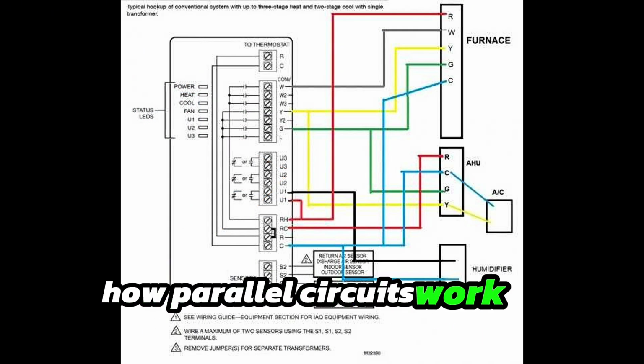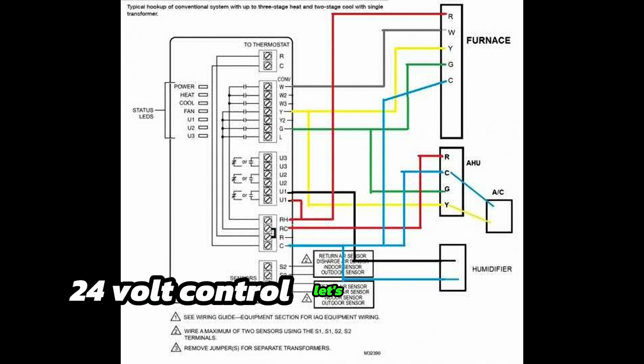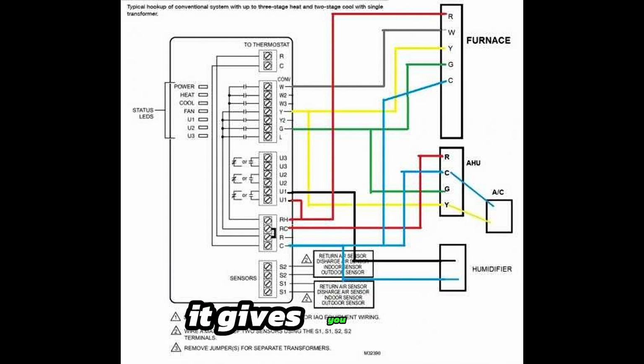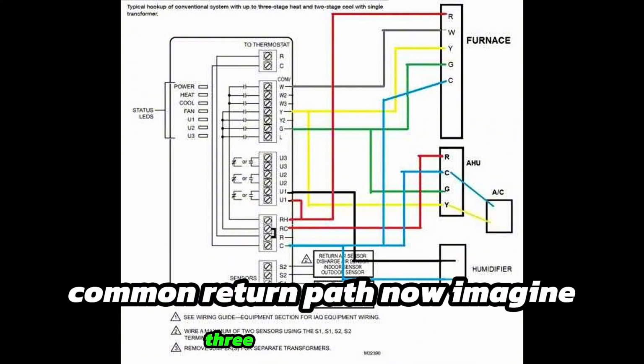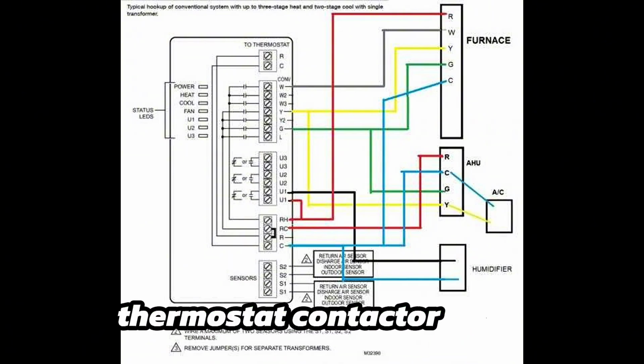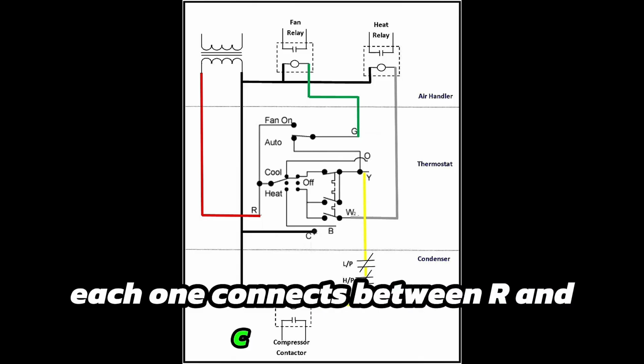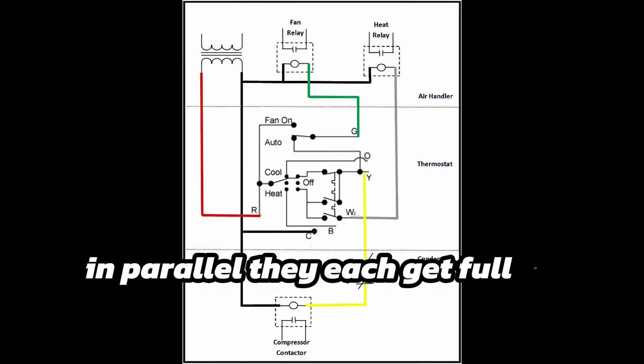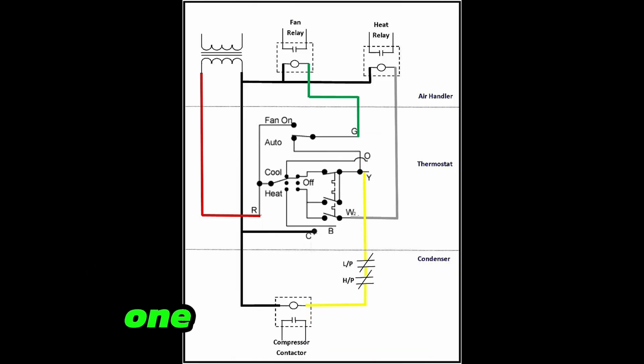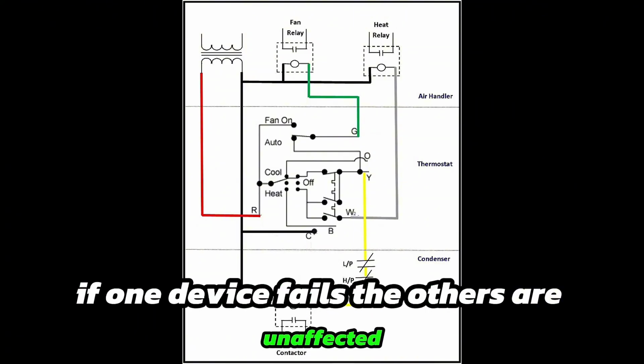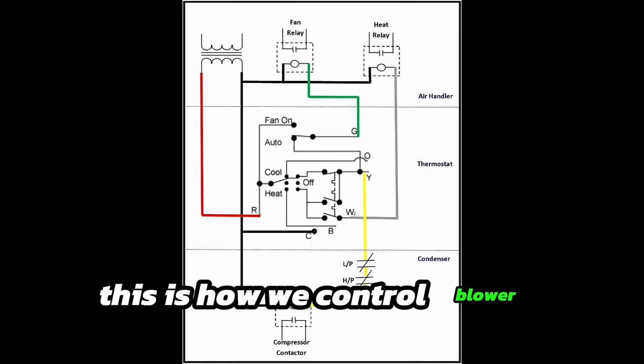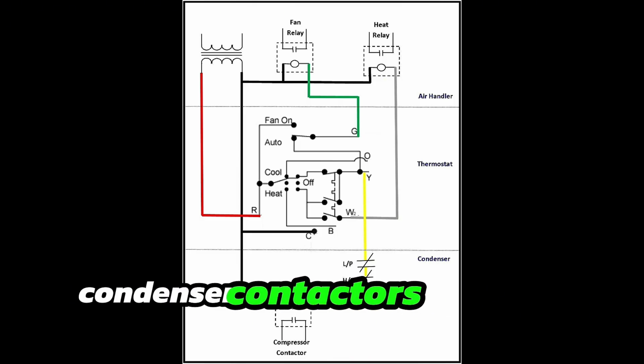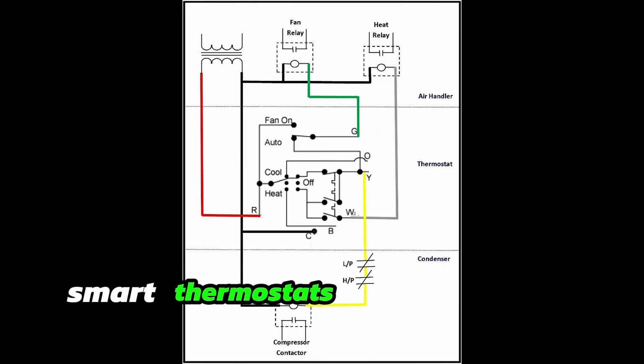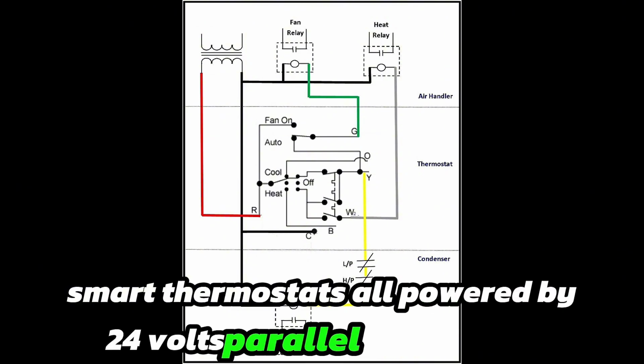How parallel circuits work in HVAC, 24-volt control. Let's say you have a 24-volt transformer. It gives you R, red, 24 volts hot, and C, common, the return path. Now imagine three components: thermostat, contactor, relay. Each one connects between R and C separately, in parallel. They each get full 24 volts because they have two wires, one wire from R, one wire to C. If one device fails, the others are unaffected. This is how we control blower relays, condenser contactors, reversing valves, and smart thermostats, all powered by 24-volt parallel connections.